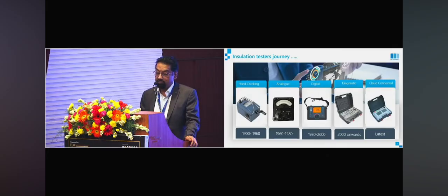People were demanding multi-parameter insulation testers. They didn't want only an insulation tester, they wanted polarization index measurement, dielectric absorption ratio measurement, step voltage measurement, breakdown voltage measurement, and many more in the same equipment. And they wanted these readings to have PC connectivity. So this was the age. In 2000 it became more popular, where people started demanding PC connected insulation testers.